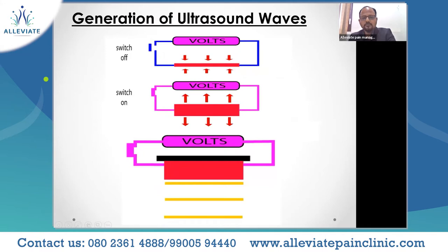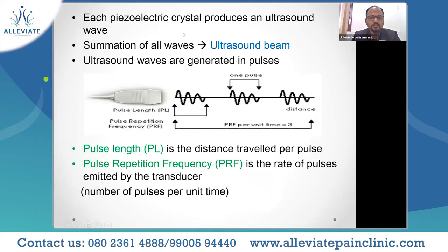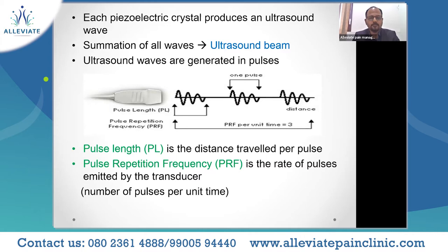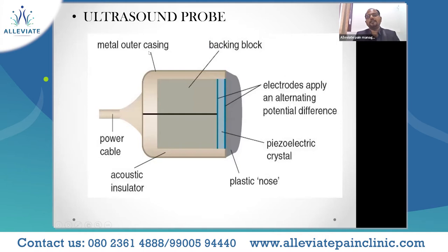Each piezoelectric crystal produces an ultrasound wave. The summation of waves from all those crystals produces the final ultrasound beam. The ultrasound waves are generated in pulses. Pulse length is the distance traveled by each pulse, and pulse repetition frequency is the rate of pulses emitted by the transducer — the number of pulses generated per unit time. Looking at the cut section of the common transducer: the most important element is the array of piezoelectric crystals in light blue, surrounded by electrodes which supply the alternating potential difference (voltage).